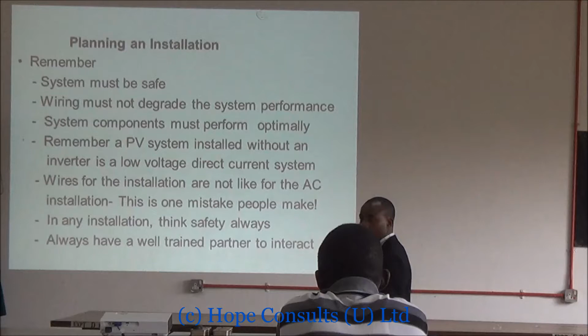Make sure components perform optimally. Remember, a PV system installed without an inverter is a low voltage direct current system. If you have no inverter, you are just using a few DC appliances, and the wires needed are not like those for AC installation. This is one mistake some people make. You should get wires different from the single strand wires used for AC wiring, like those used in the lecture theater or in second year connections.